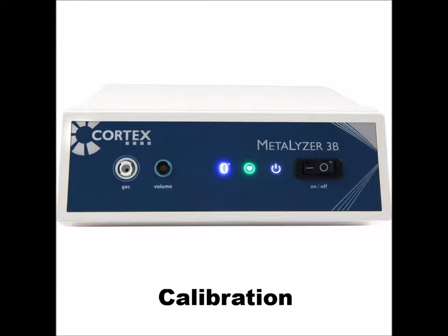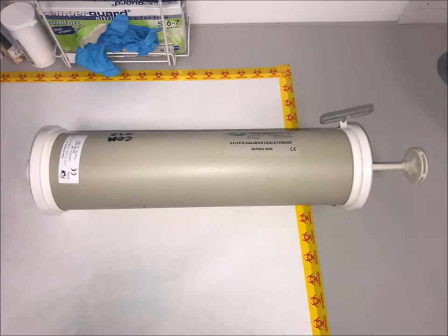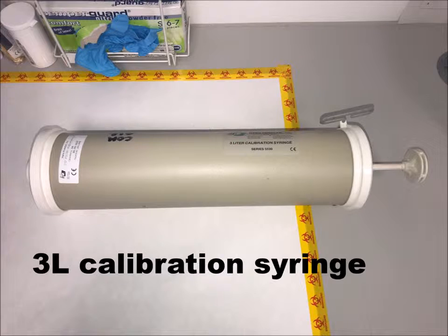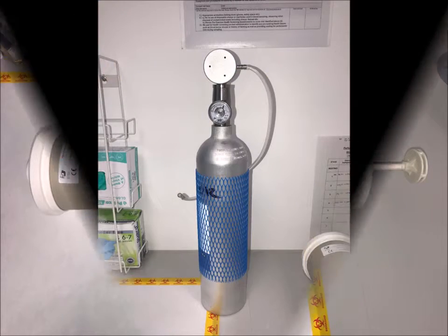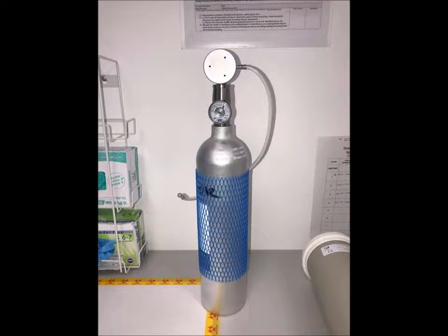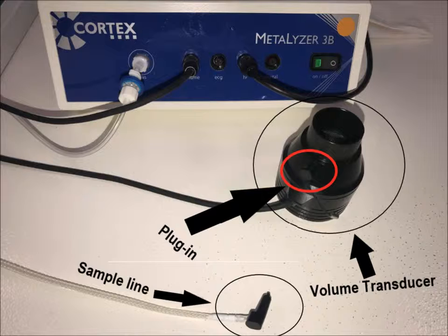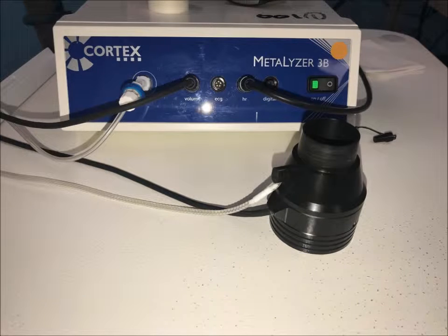To allow the Metalyzer 3B to collect appropriate and the highest possible precise data, calibration is compulsory before it can be used. For calibration, the following equipment is required: a 3-litre calibration syringe, certified calibration reference gas, a sample line, which is then linked to the volume transducer, which should be connected to the Metalyzer, and lastly a pressure gauge.